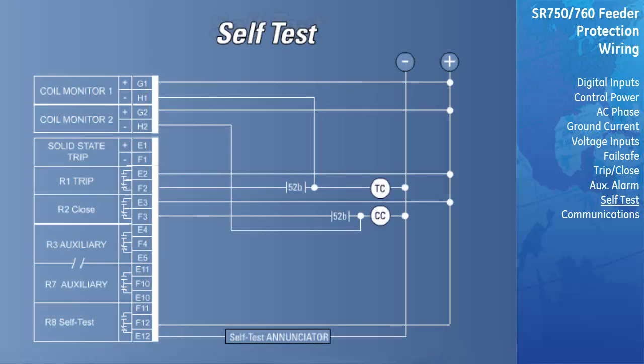The failsafe self-test relay R8 will operate, in other words, de-energize, if the relay detects an internal fault or power to the relay has been removed. This output may be monitored with an annunciator, PLC or DCS. Another application is to wire the self-test relay normally closed contact in parallel with the trip relay auxiliary on a breaker. This will provide failsafe operation of the system. The breaker will be tripped offline in the event that the relay loses power or has an internal failure and is unable to provide protection.